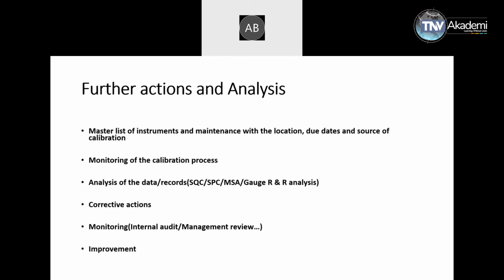Many organizations go away or try to reduce this, or try not to get into the calibration system because they feel it is very costly. It increases the cost of production and inspection and calibration. So from this place, when we do the analysis and when we go to corrective actions, we can bring out the facts and figures. Yes, initially it may look costly, but if we compare it with the rejection and rework which happens because of the wrong instrument, because of uncalibrated instruments, because of incorrect inspection, because of an untrained calibration team, these costs are much higher than the cost of calibration actually. So these things are important.